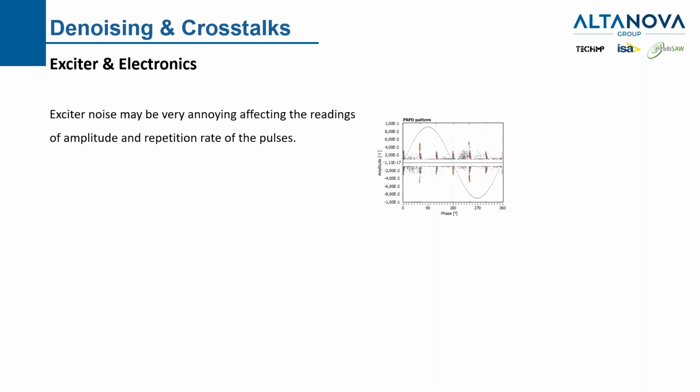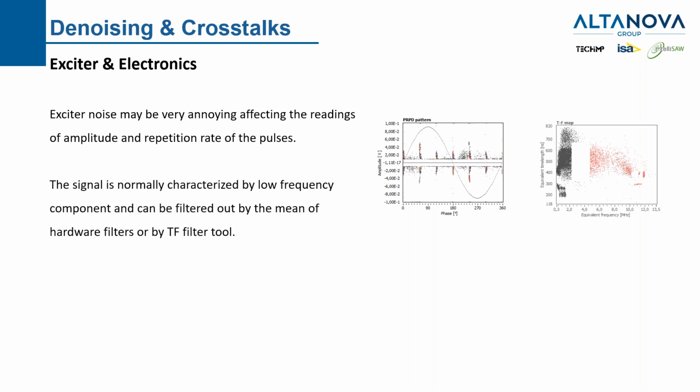There is a clock on the exciter giving such disturbances, normally from the insulated gate bipolar transistors of the exciter, and we can find them very often. A very good thing for us is that this signal's frequency spectrum is normally far from the PD signal frequency spectrum.